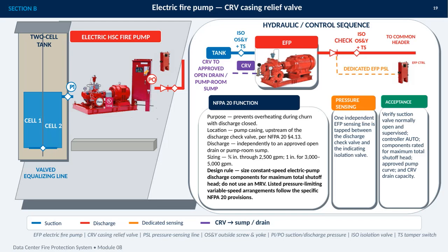This slide shows the hydraulic and control arrangement for an electric horizontal split case fire pump, or EFP, serving a 2-cell tank. The tank cells are connected by a valved equalizing line, while the pump suction and discharge sides include supervised isolation valves, pressure indicators, and a discharge check valve.